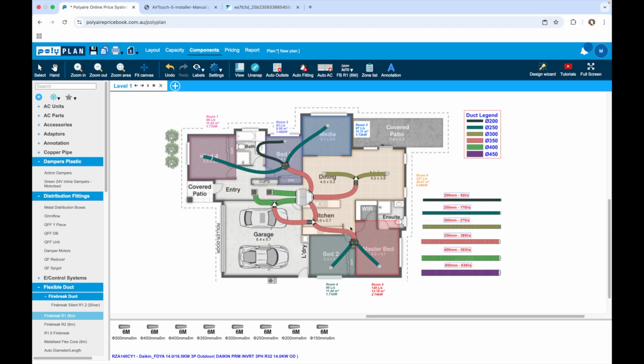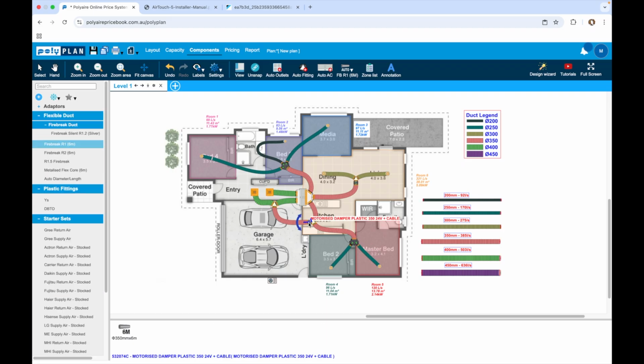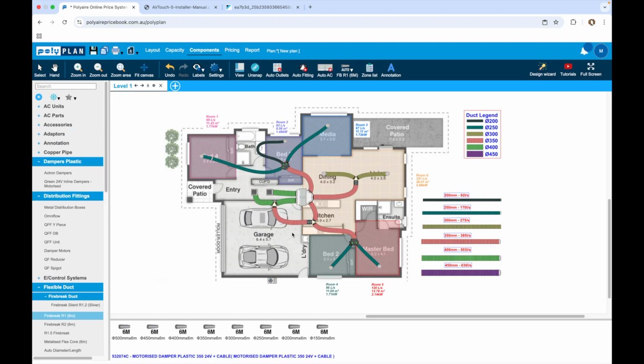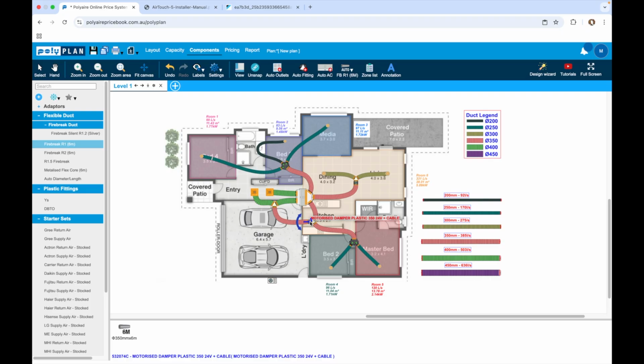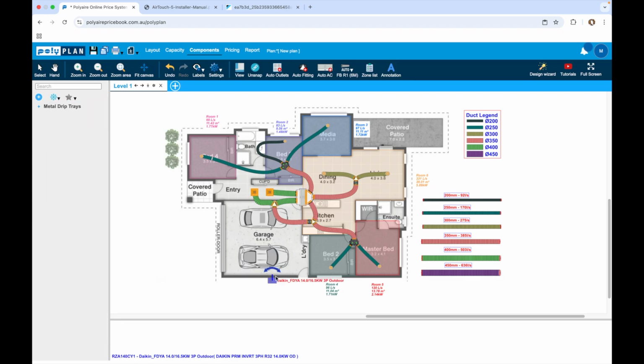The other main thing it does, it seems like a lot of tradesmen aren't even aware of, is that as this is opening, because it opens incrementally, as this opens and cold air starts going back to this and mixing with this air from your return, it actually starts telling this unit to slow down much sooner. It doesn't just force it to stop.